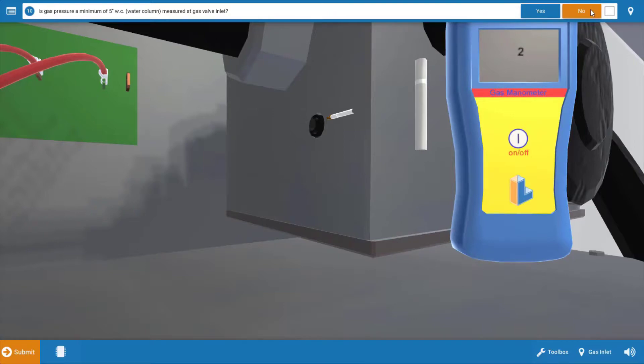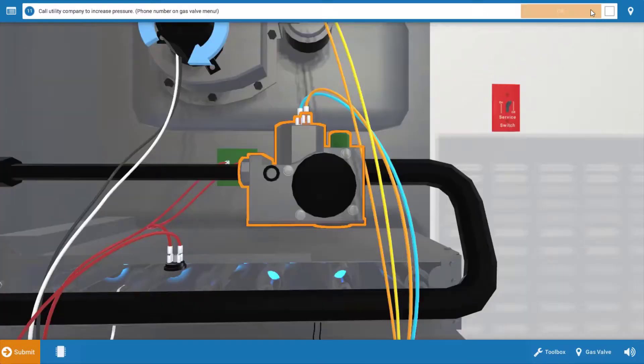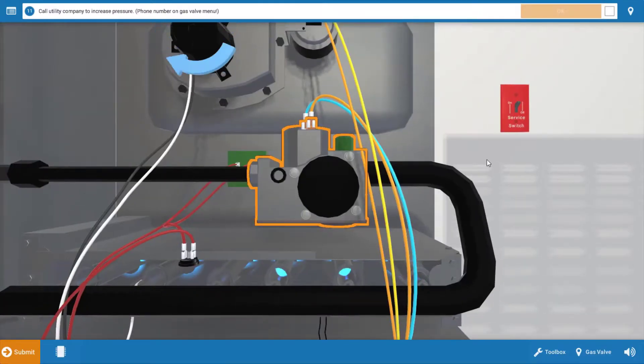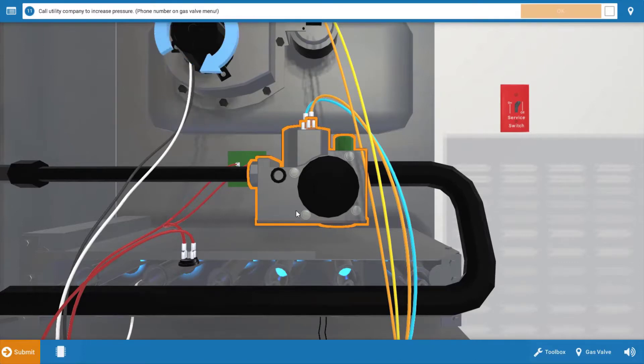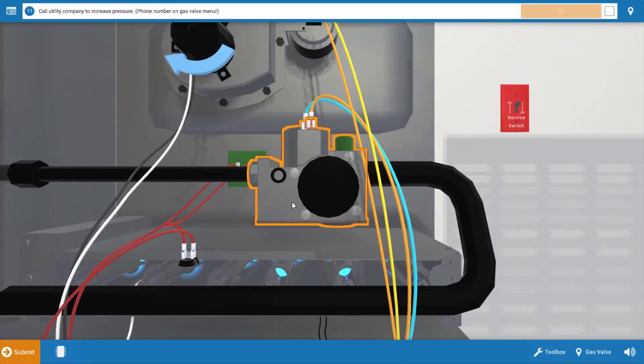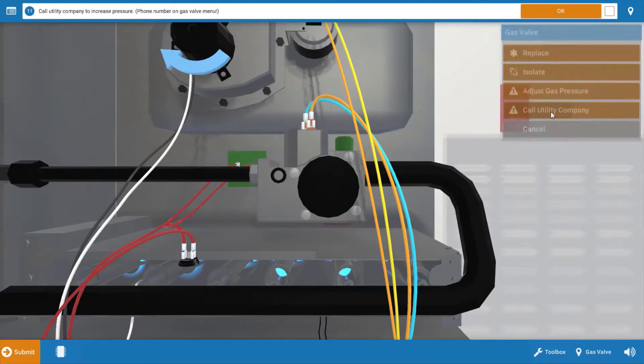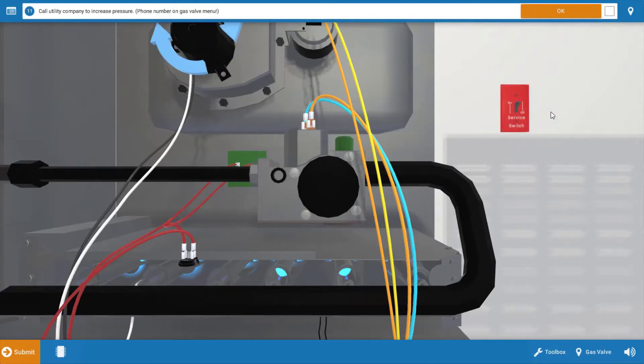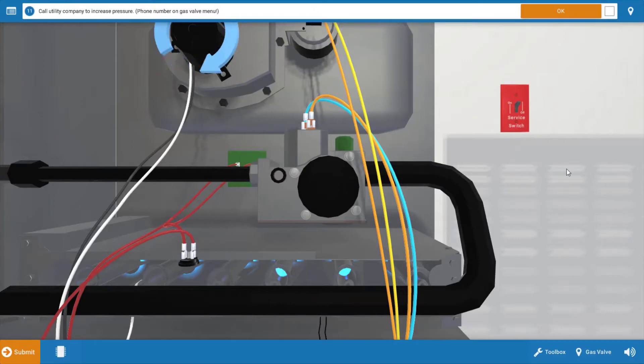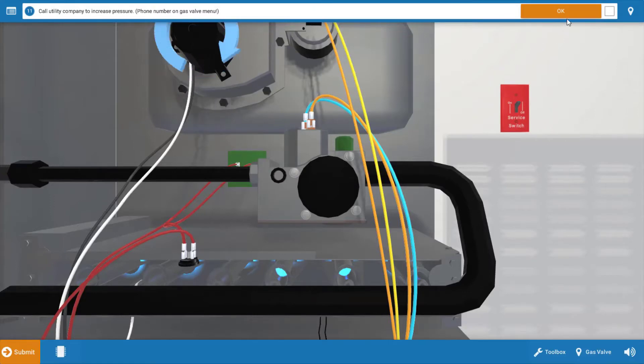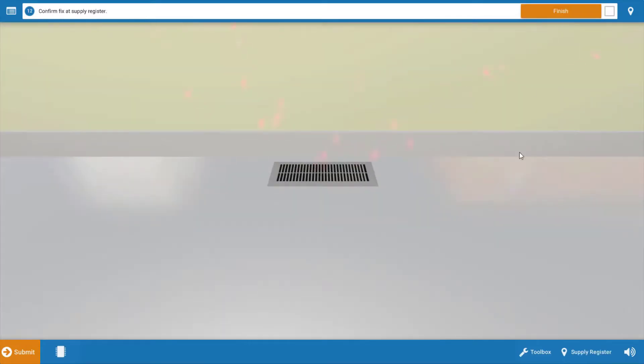So after we click no on the procedure guide that we don't have a minimum of five inches, we're going to click on the gas valve. Now, we're not replacing the gas valve here. There's nothing wrong with the gas valve. But on the menu, we're going to say call utility company and they'll come out and solve the problem for you so that you have that acceptable gas pressure coming in. Click OK on the menu and that's going to solve the problem.